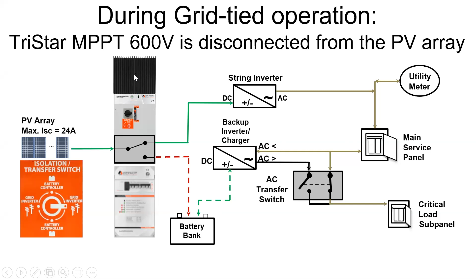And while the grid is operational, again, you'll get the power produced from your array through the output of the string inverter to your main service panel. Again, some of that power will be relegated to charge the battery when the AC transfer switch is in the opposite position. So again, it's going to change based on your operating mode. The AC transfer switch does so automatically. When the grid is lost, you'll change over to inverter and pick up the critical loads, basically as a UPS, depending on how responsive the inverter charger is. The automatic AC transfer switch will turn into inverter mode when grid is lost, so that you can take the power out to the critical loads.